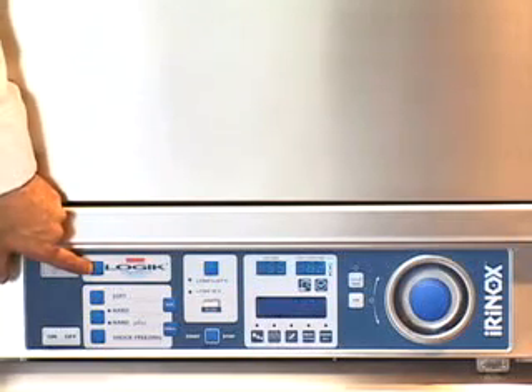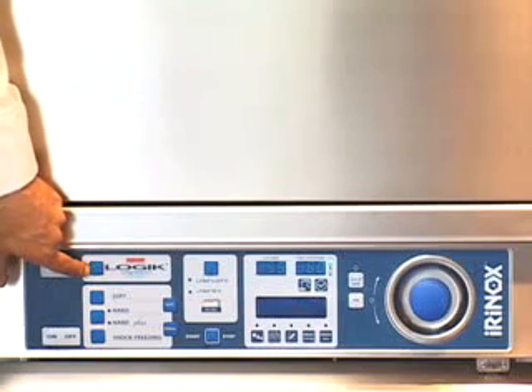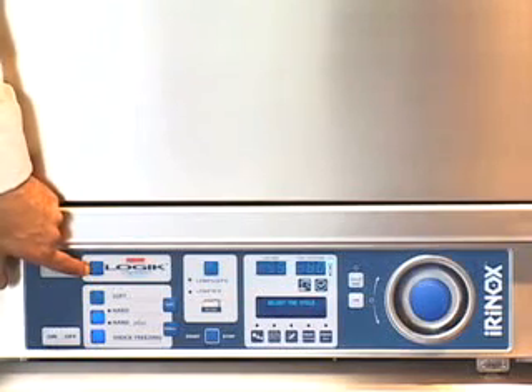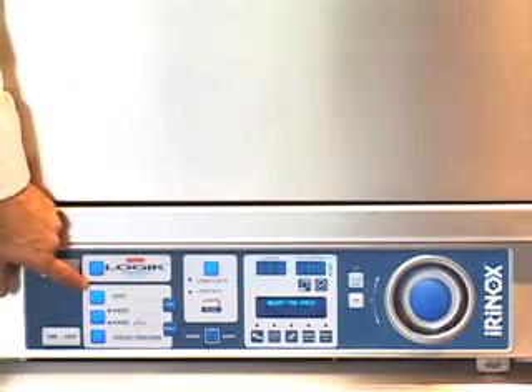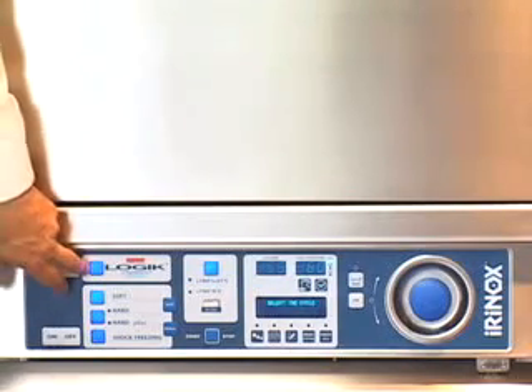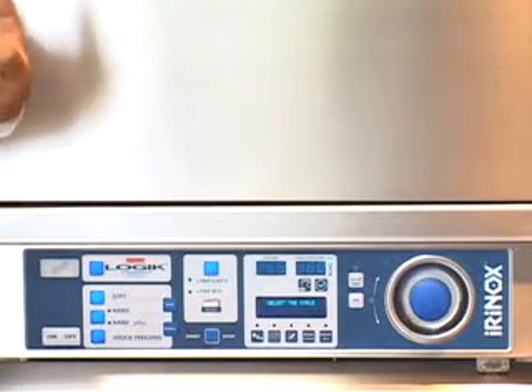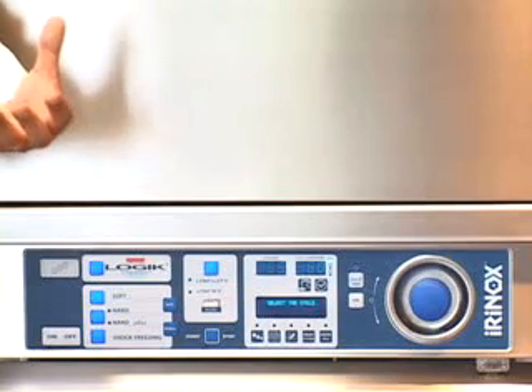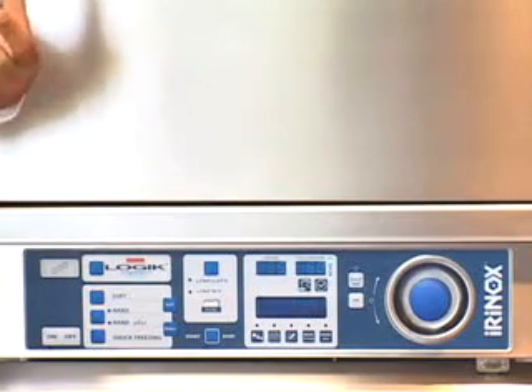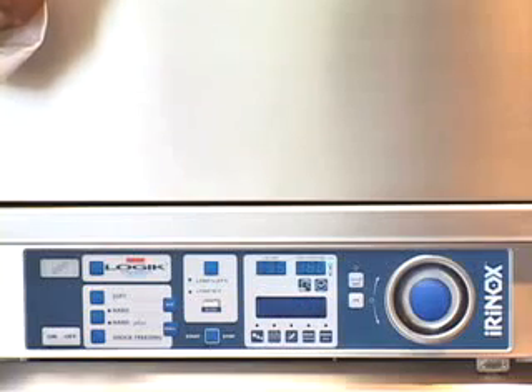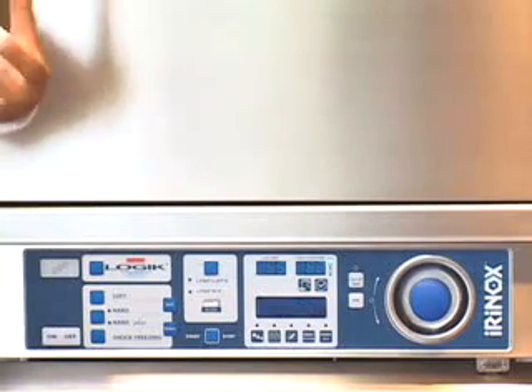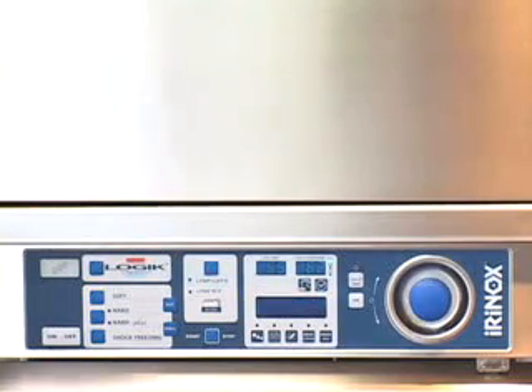It requires the use of the probe, and you should use that if you are not sure of whether you should use soft, hard, or hard plus chilling. It will automatically monitor the core temperature of your product, and adjust the air temperature in the cabinet appropriately to maximize the efficiency and chill the product as quickly as possible without damaging it.